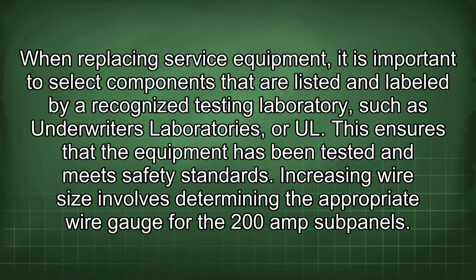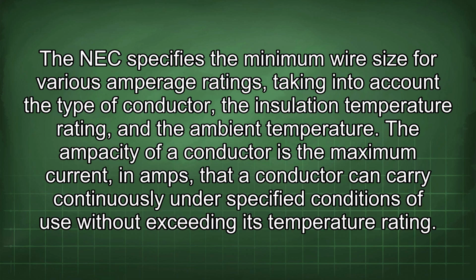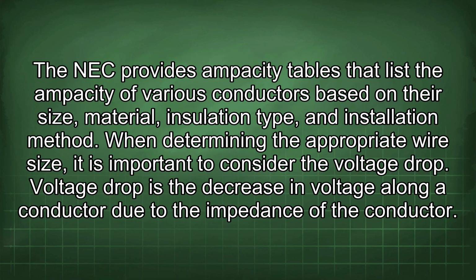Increasing wire size involves determining the appropriate wire gauge for the 200 amp subpanels. The NEC specifies the minimum wire size for various amperage ratings, taking into account the type of conductor, the insulation temperature rating, and the ambient temperature. The ampacity of a conductor is the maximum current, in amps, that a conductor can carry continuously under specified conditions of use without exceeding its temperature rating. The NEC provides ampacity tables that list the ampacity of various conductors based on their size, material, insulation type, and installation method.